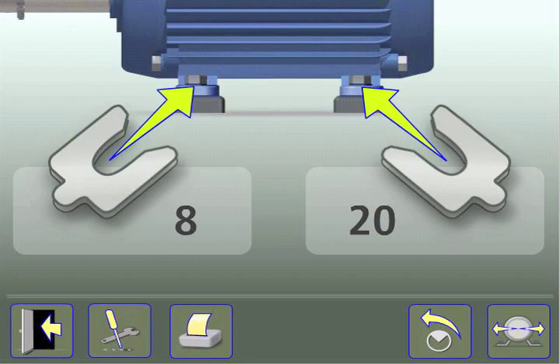In this case, both front and rear feet are sitting low. Therefore, shims are added equal to the feet values displayed. Eight thousandths are added to the front feet and twenty thousandths to the rear feet.